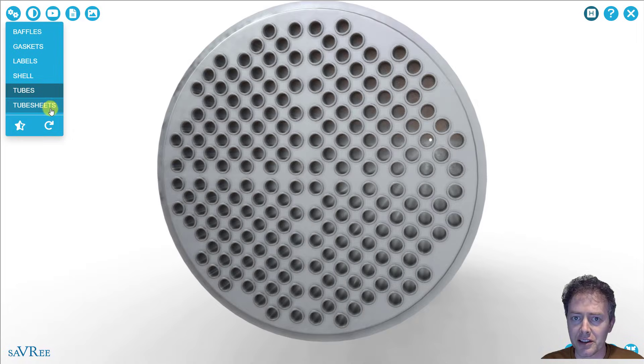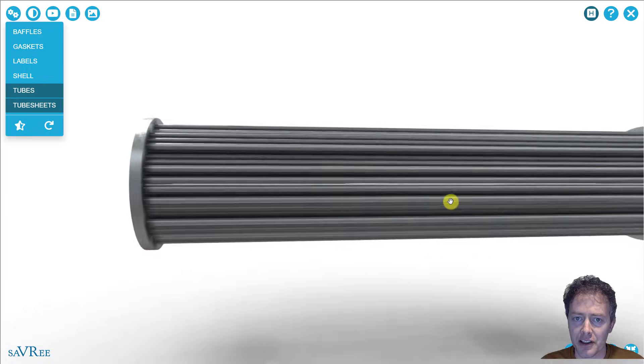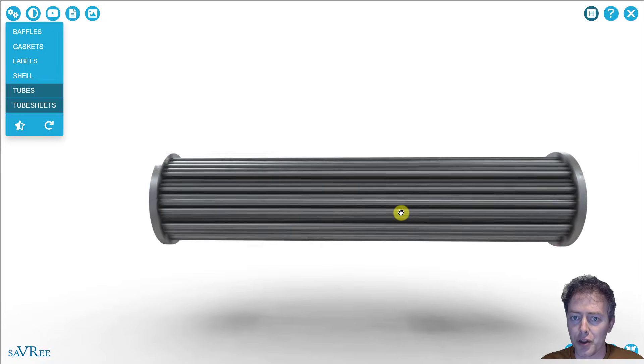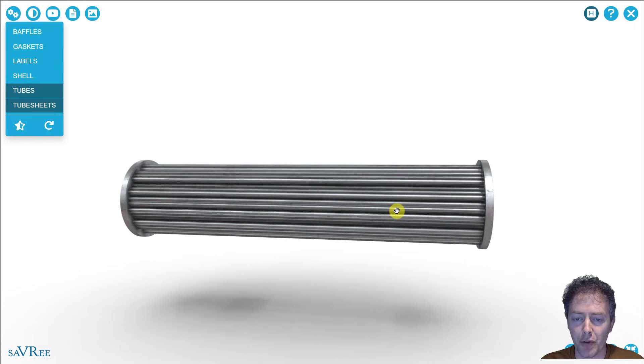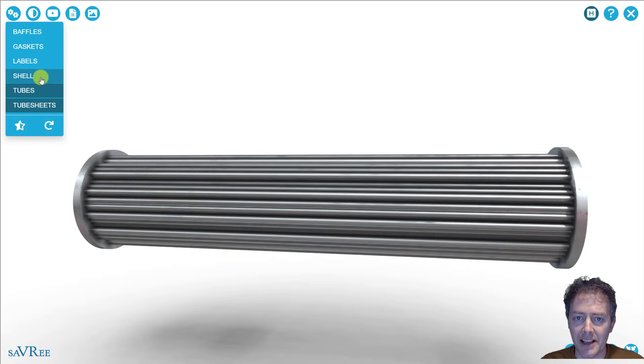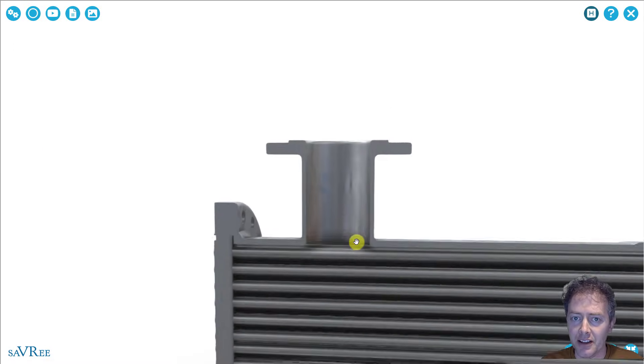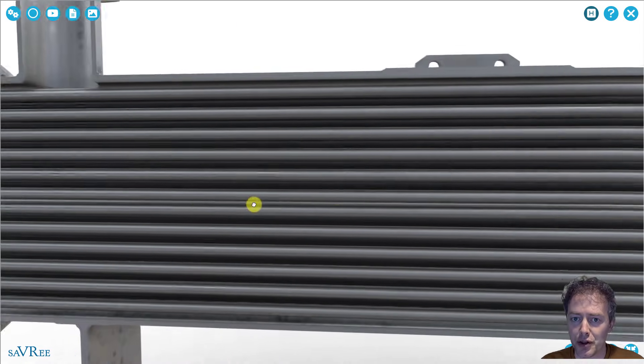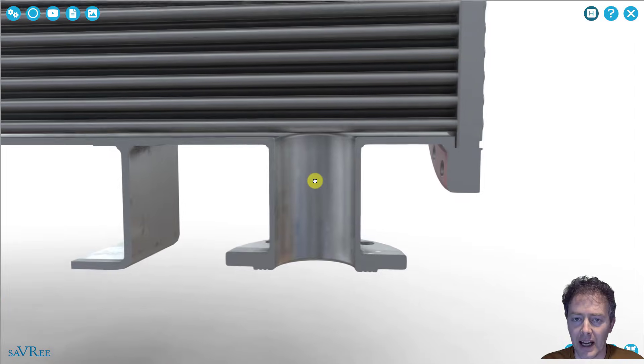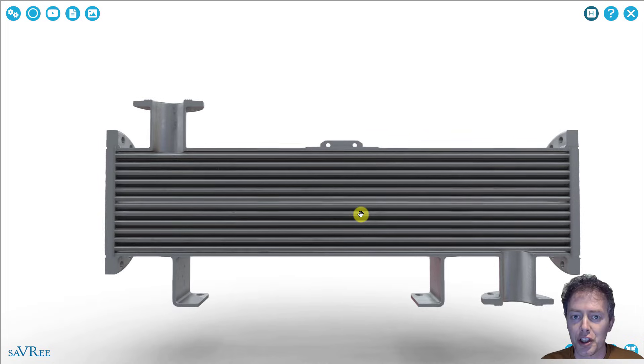The tubes are essentially long pipes that have been placed within our heat exchanger shell. We put tube sheets on the ends of our tubes — this ensures that the tubes stay in position. There's a tube sheet at either end. Those tube sheets give the tubes mechanical strength and also provide a seal so that the shell side fluid flowing around the outside of the tubes doesn't leak out from our shell.